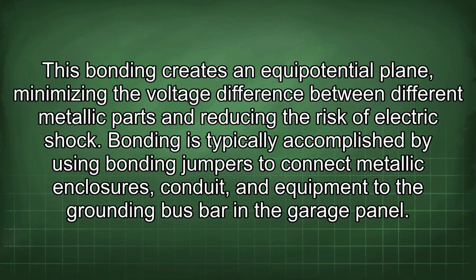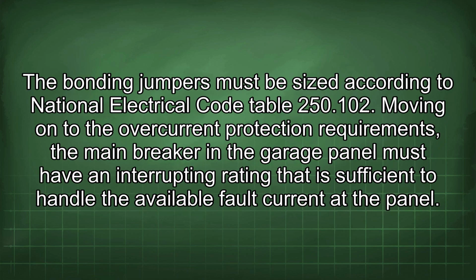shock. Bonding is typically accomplished by using bonding jumpers to connect metallic enclosures, conduit, and equipment to the grounding bus bar in the garage panel. The bonding jumpers must be sized according to National Electrical Code Table 250.102.